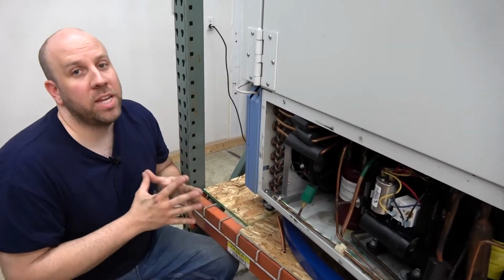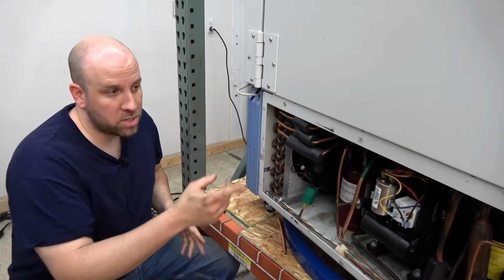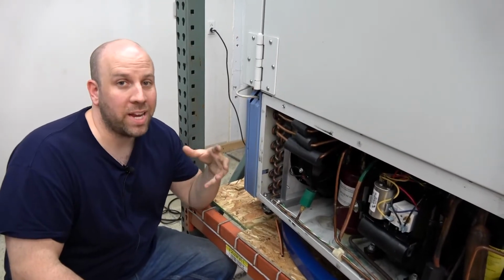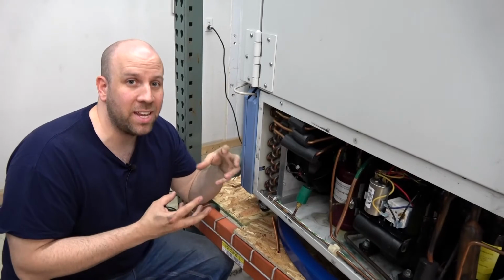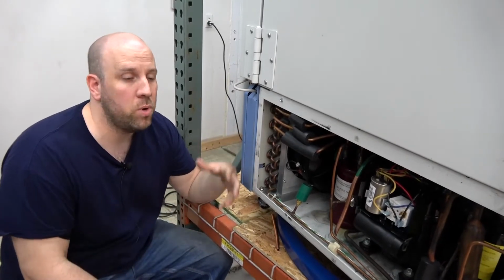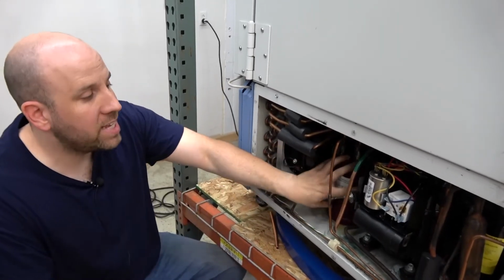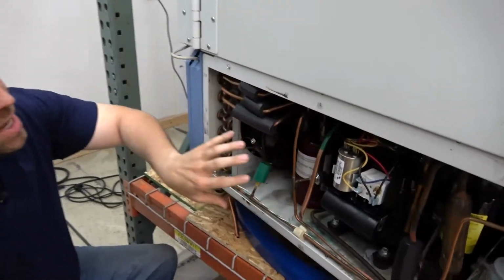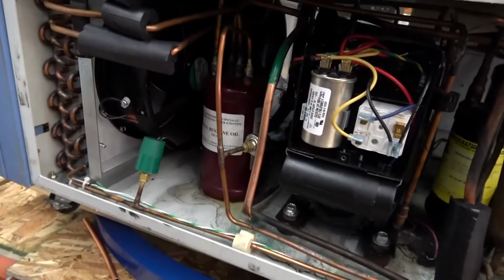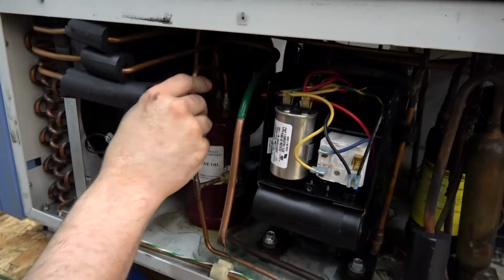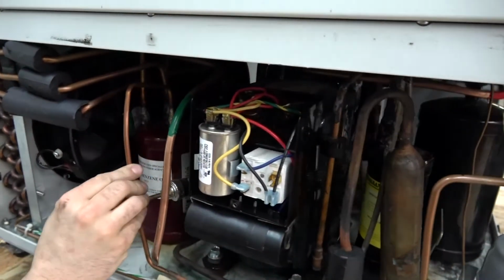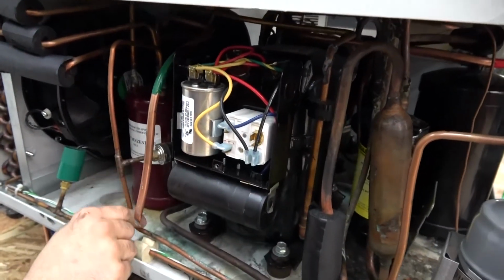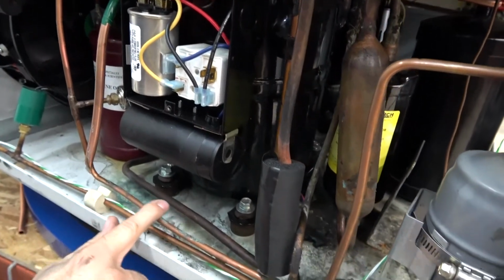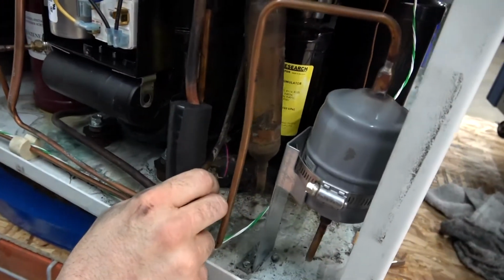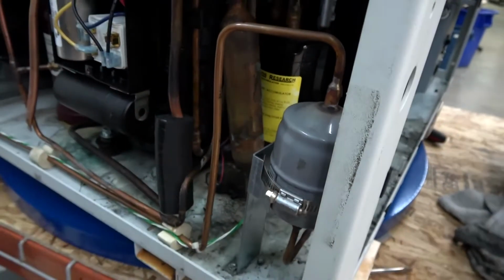And as you get into tight spaces like the capillary tube we talked about, the oil can cause restrictions because it's thick and gets really viscous, especially when it gets cold. So on the second stage, when you're dealing with really low refrigeration, it separates out the oil to prevent those things from happening. So coming out of here, you should have pretty much, for the most part, oil-free refrigerant in the gas state, or yeah, it should still be in the gas state.